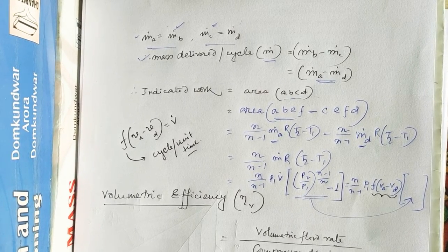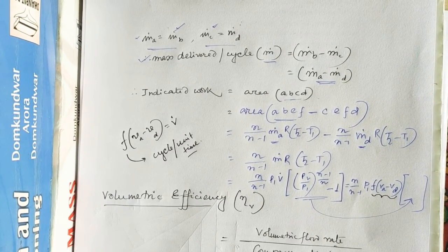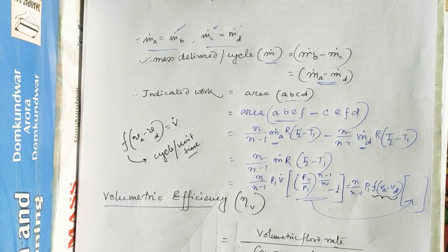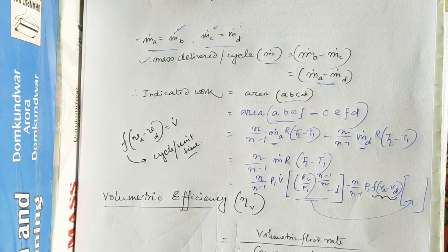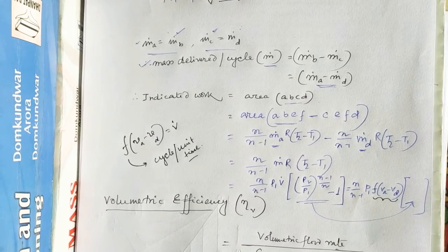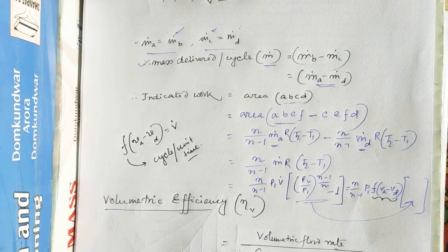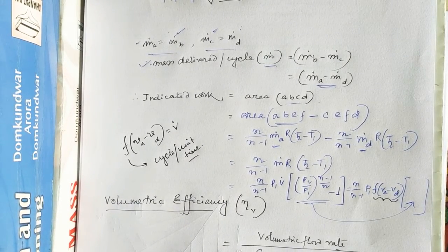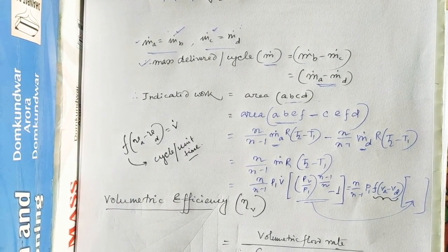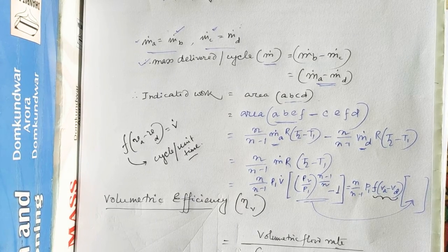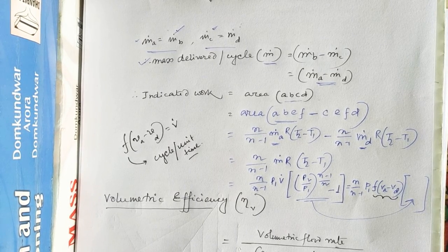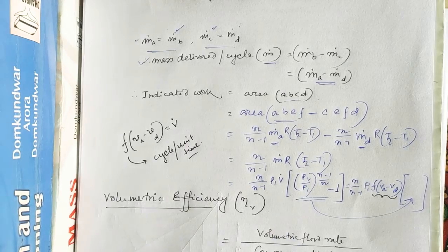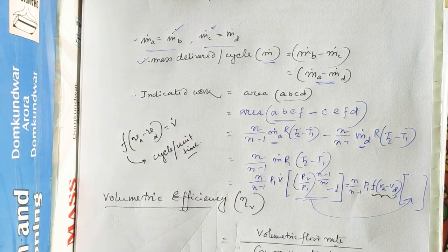So for a given condenser and evaporator pressure, some important performance parameters are there. The first parameter is the mass flow rate of the refrigerant that will enter the compressor for a given displacement volume. Second is the power consumption of the compressor. Third is the temperature of the refrigerant at the exit of the compressor, and the fourth one is performance under part load conditions.